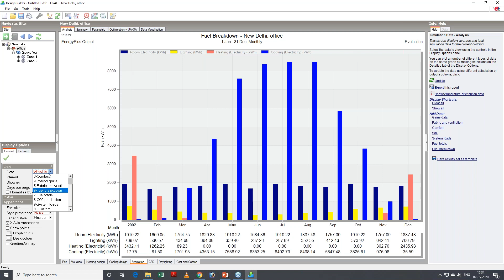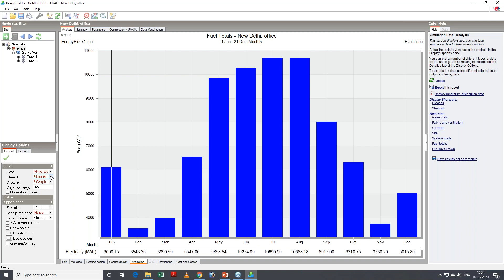Then fuel total, this is the fuel total monthly consumption, in which February is the month with the least energy consumption, and July is the month which has the highest energy consumption. When I select the run period, that is annual energy consumption, and I use it normalized by area. So this data is the EPI of the building. You can say 168.75 kilowatt per meter square is the energy performance index of this building.